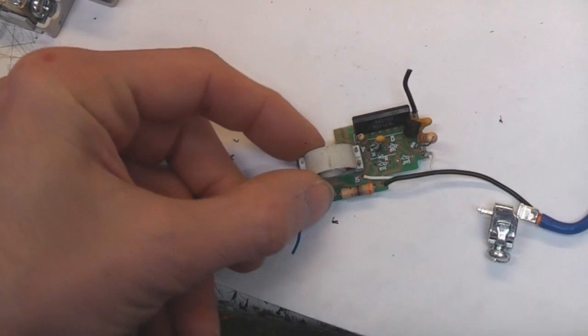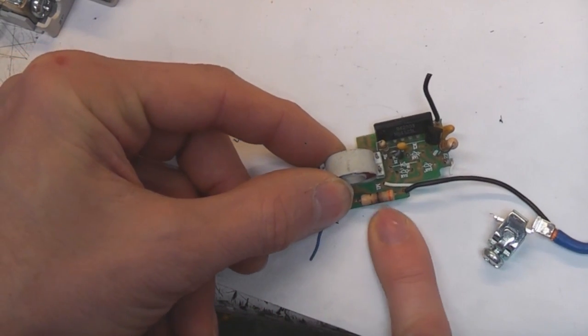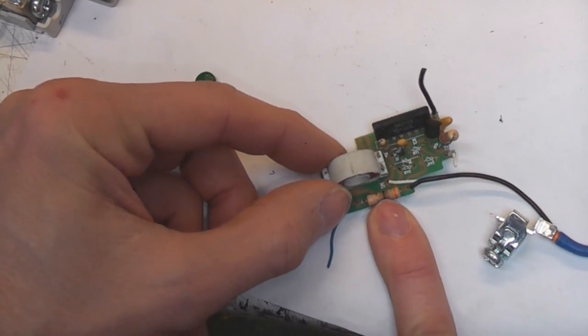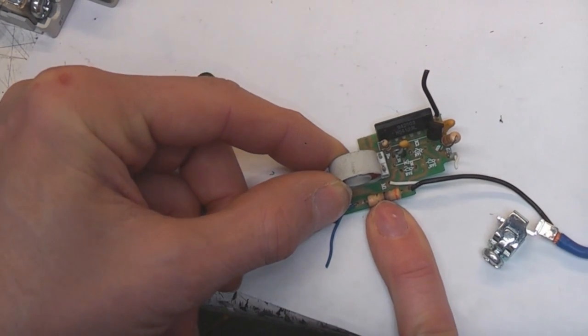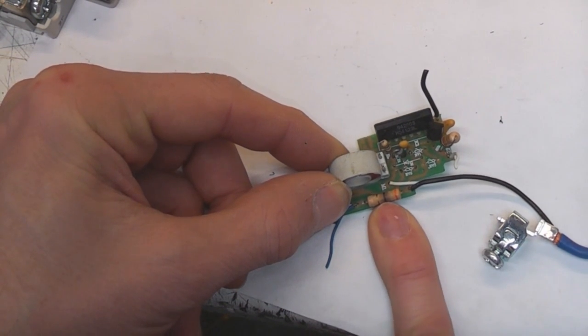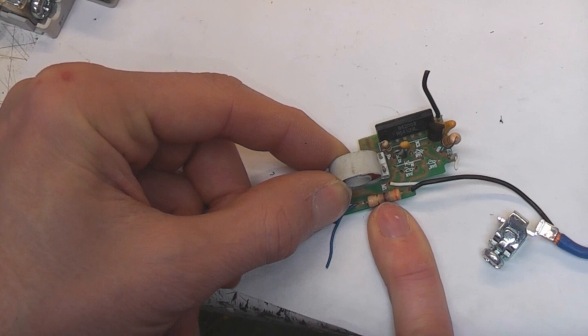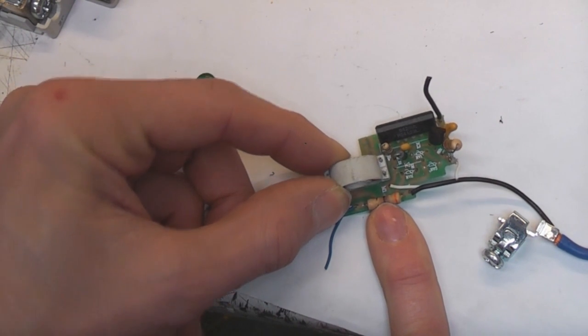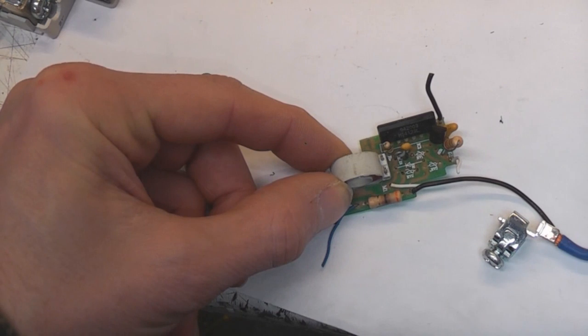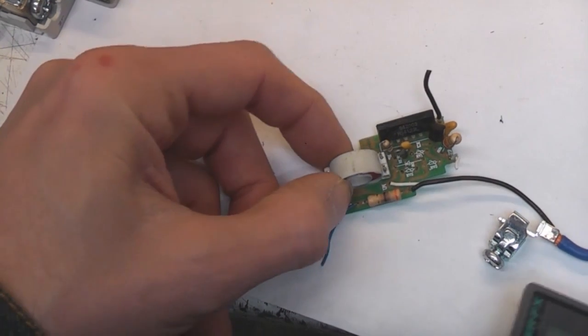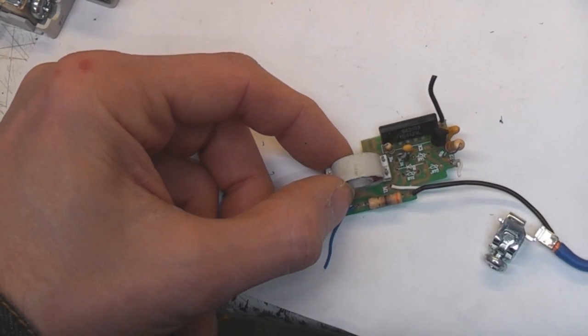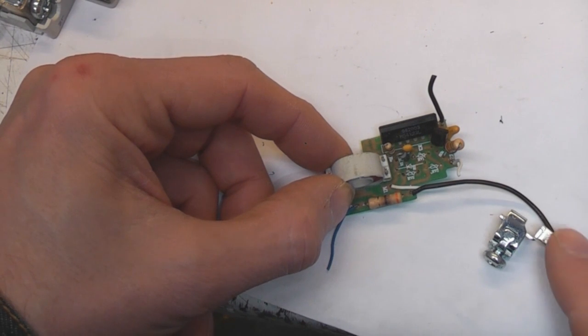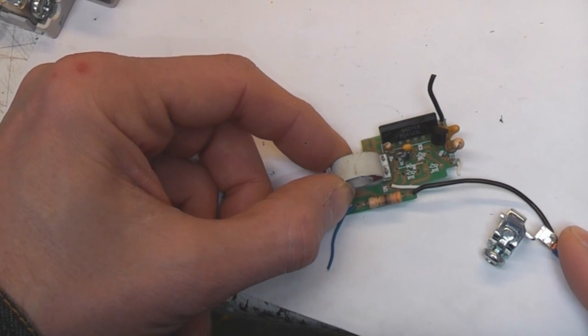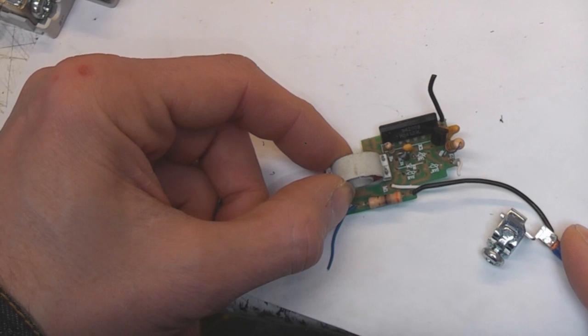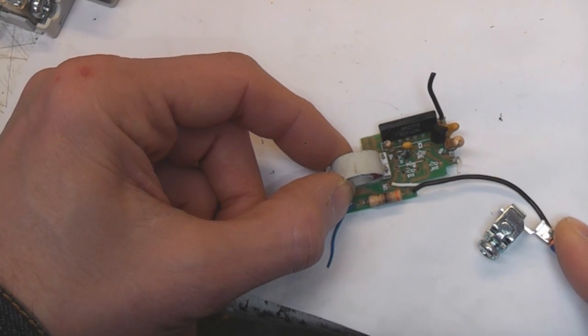One thing I was a little bit curious about: this is a 3.9k resistor that looks a little bit crozzled, and this is the current limiting resistor for the test button. You wouldn't think that should be operated for anything but very brief periods of time, so it's a bit curious as to why it's burnt. Now, if we work out the current, that's 3k9, so at 240 volts that'll produce 60 milliamps of fault current across the transformer, which is twice its rated trip current, so that's probably just to make sure it trips.